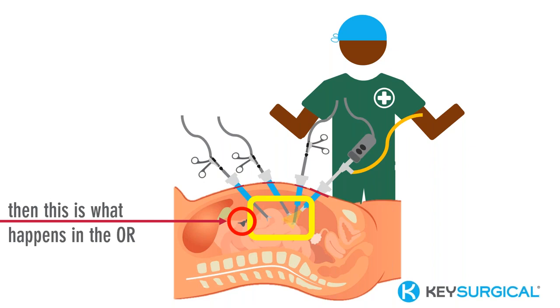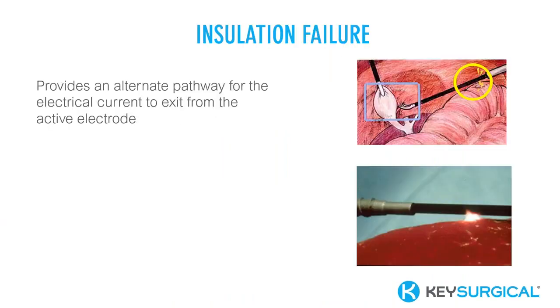So remembering that 1 in 5 of the reusable instruments have damage that they've found in this research study, and actually 67% of that injury is not noticed at the time of injury. We did talk about this at length at the beginning, but we'll restate just a couple of things. Insulation failure provides an alternate pathway for that electrical current to leave the instrument and can cause unintentional patient injury. So some best practices to avoid insulation failure or to notice it, right, is to test 100% of insulated instruments, every single one, in sterile processing before assembling them for sterilization.